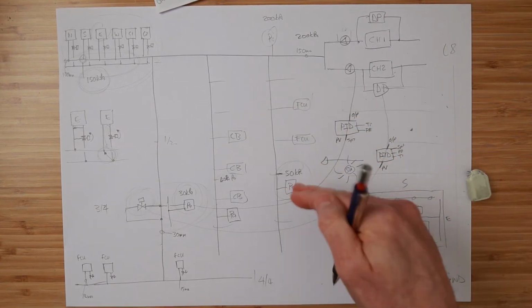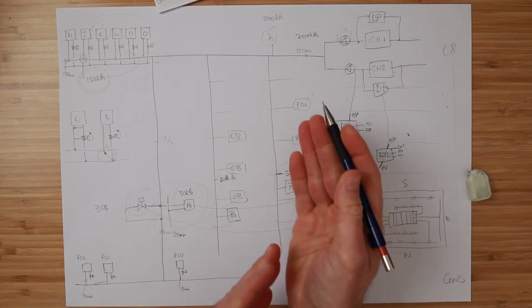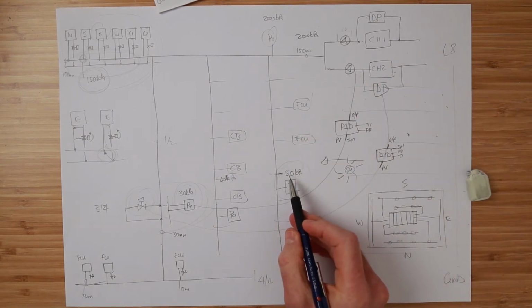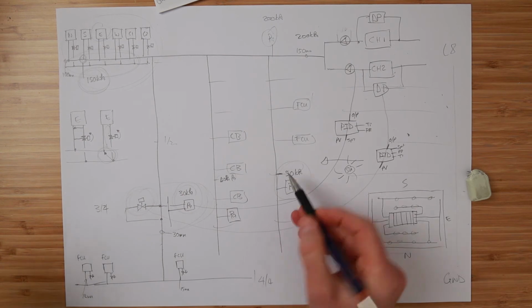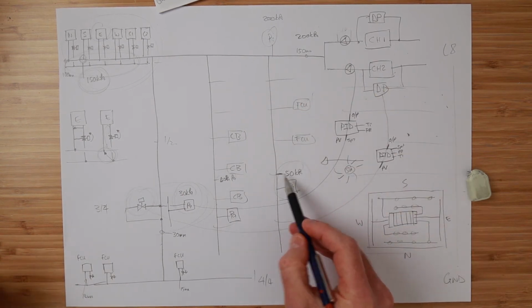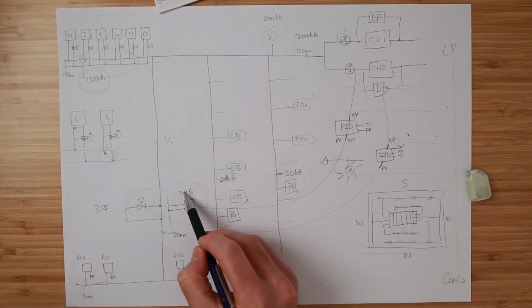This pressure could be quite low. So we need the pump to push this pressure up to hold the design here so that the valve authority is correct for the fan coil units. That would result in this being a little bit too high, a little bit too high, a little bit too high. But at least you have enough pressure everywhere. We're not starved of pressure.